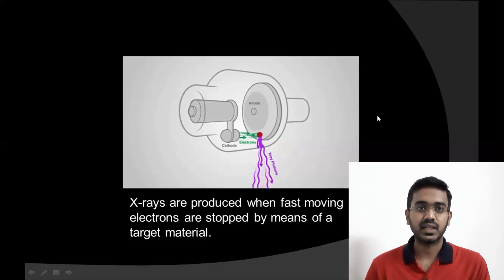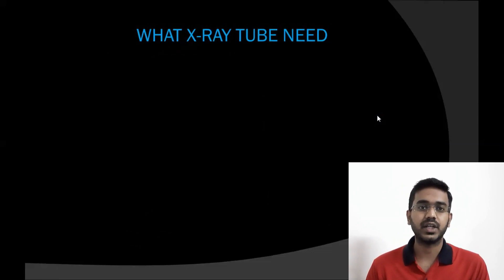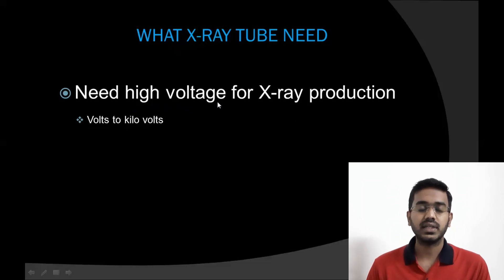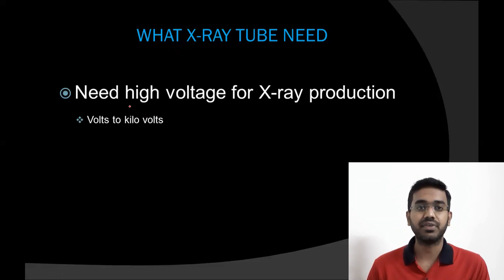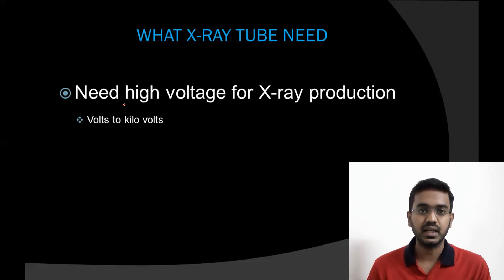Next, let us discuss the components in the X-ray tube. The X-ray tube needs high voltage for X-ray production. Why do we need high voltage? As mentioned in the X-ray production principle, we need fast-moving electrons to generate X-rays. In order to accelerate the electron faster, we need to provide high potential, i.e., high voltage.